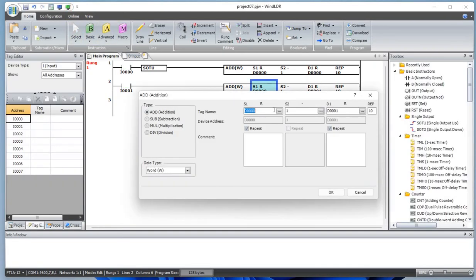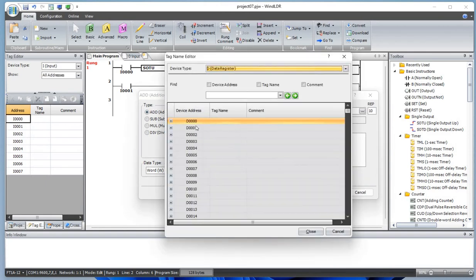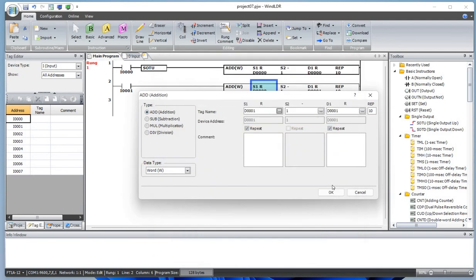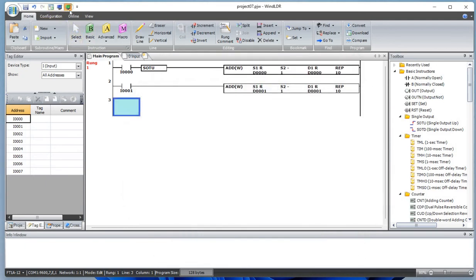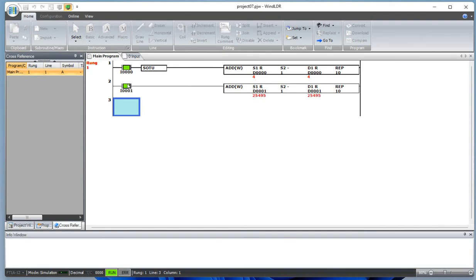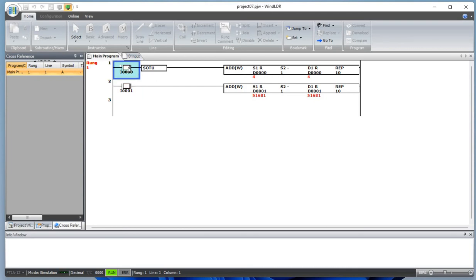This source should be data register D1 and save to D1. Let's run the simulation. Since input I1 is on, it's counting very rapidly and adding to D1. Now let's turn it off. The other one — using SOTU — is counting only on the rising trigger. That's the difference between using SOTU and not using SOTU.